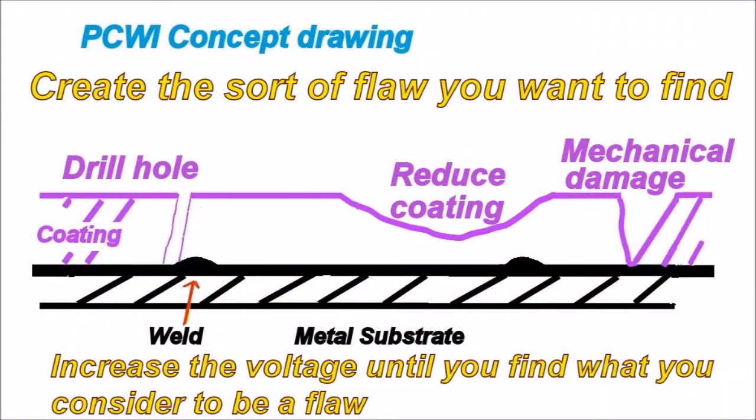Now, as far as voltages go, maybe you need to prove that you can find the sort of flaws that you're looking for. If you drill a hole, for instance, and pass the coil over it or the brush over it, and you continually increase the voltage until you find it.